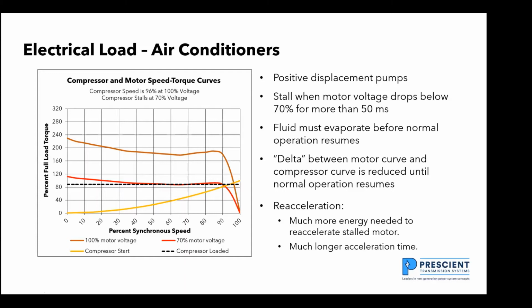And this means that when I'm reaccelerating, I'm going to be putting a lot of energy in the motor for a long period of time. And normally a motor that would start in 2 seconds may not start for 20 seconds. And that means I've got a voltage dip that's going to be out there for a long, long time.